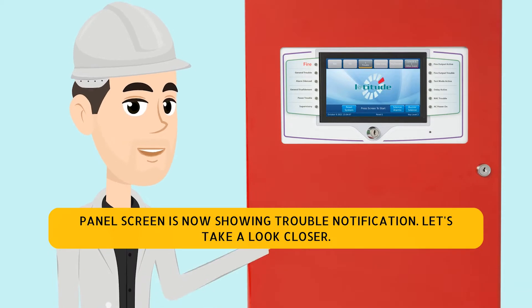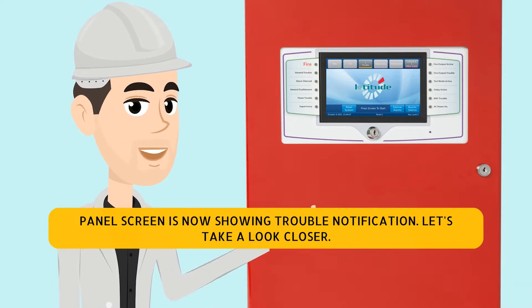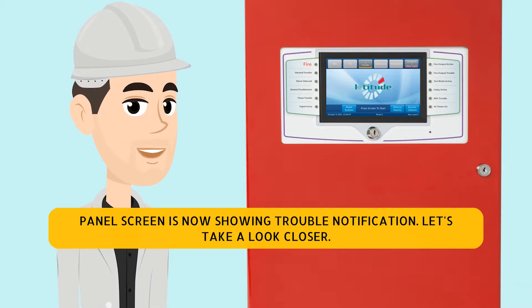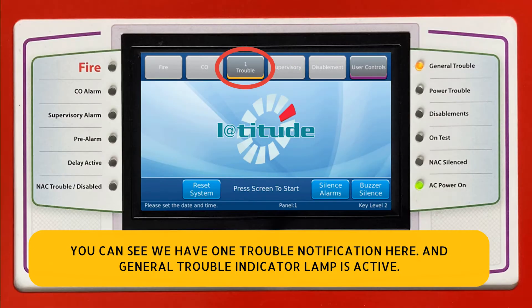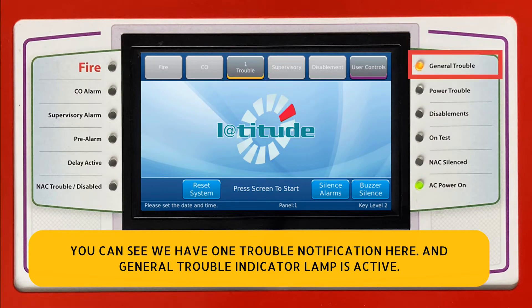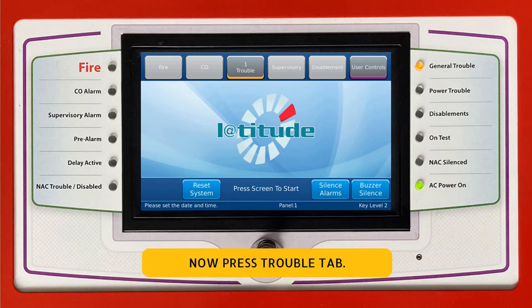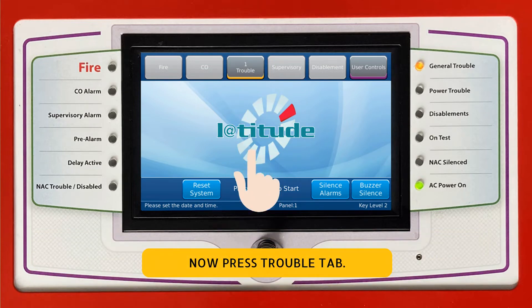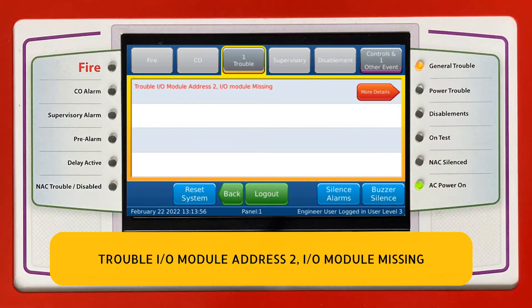The panel screen is now showing a trouble notification. Let's take a closer look. You can see we have one trouble notification here, and the general trouble indicator lamp is active. Now press the trouble tab. Trouble: I.O. module address 2, I.O. module missing.